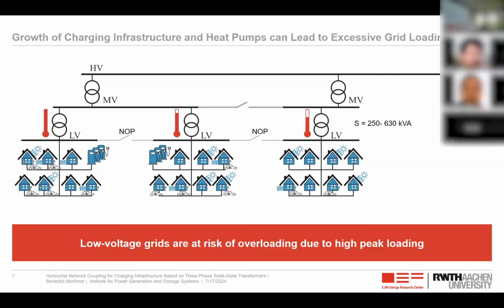But what happens now if we have more EVs, and install more and more charging stations? Then we are at the risk that these transformers will overload due to the high peak loading. And this is then typically associated with a lifetime reduction of the components, or even the destruction if there are some short circuits happening due to the degraded isolation materials.